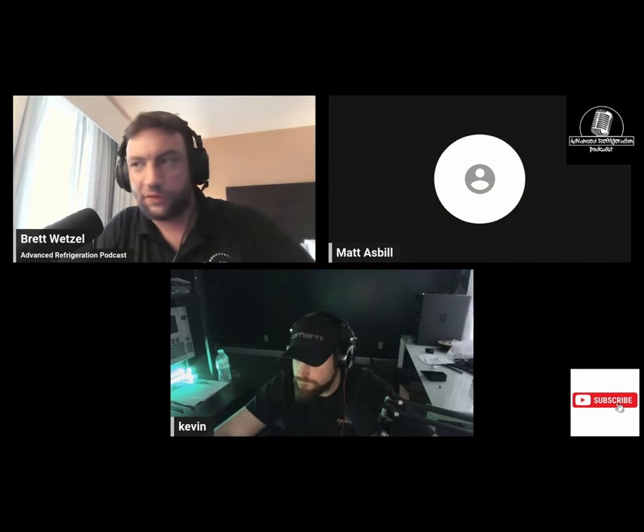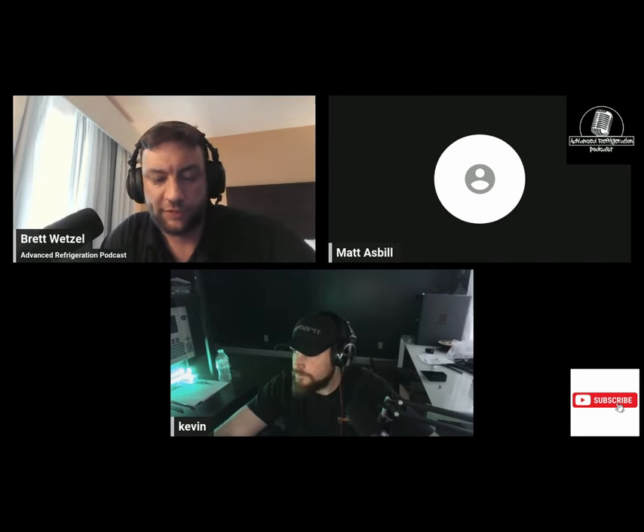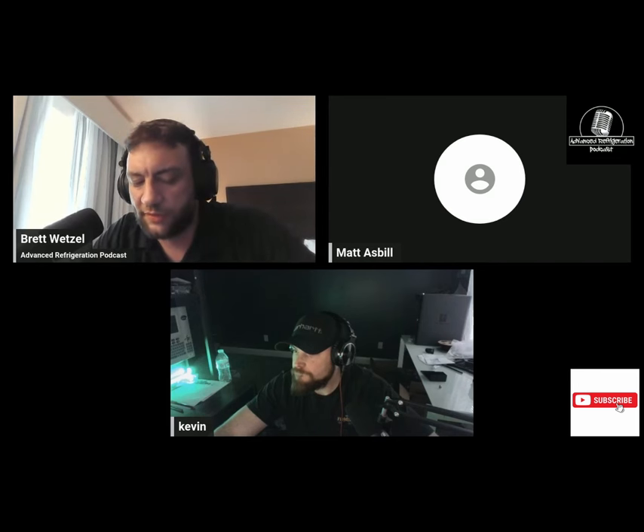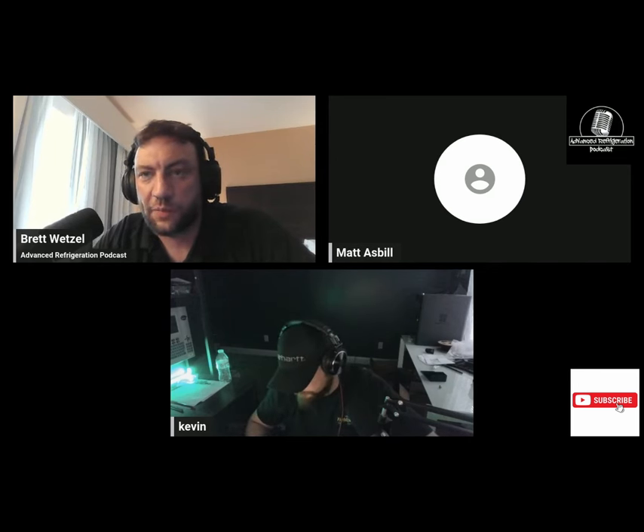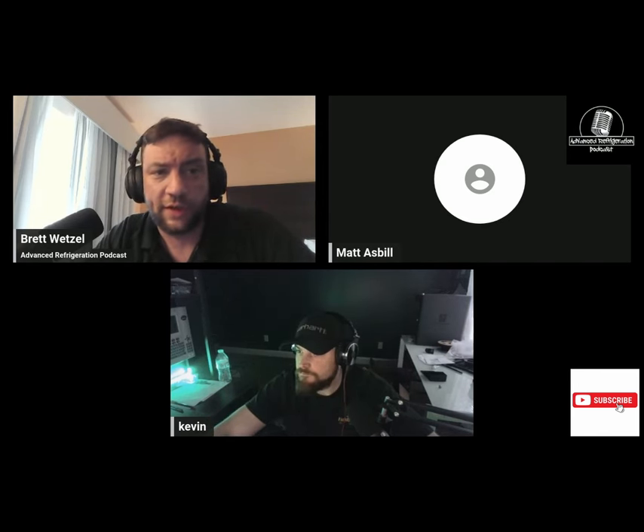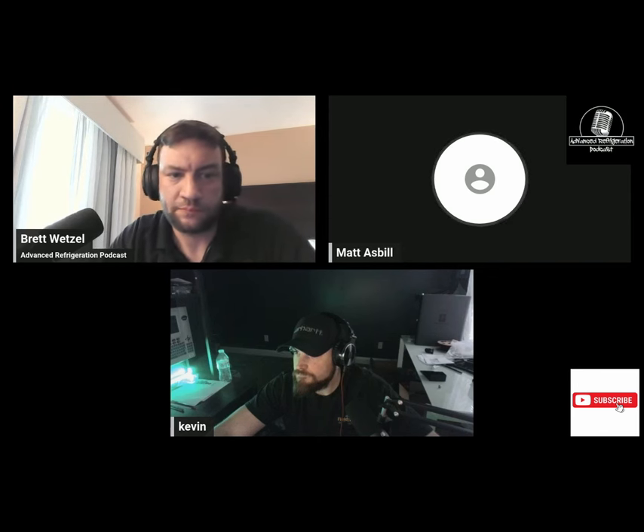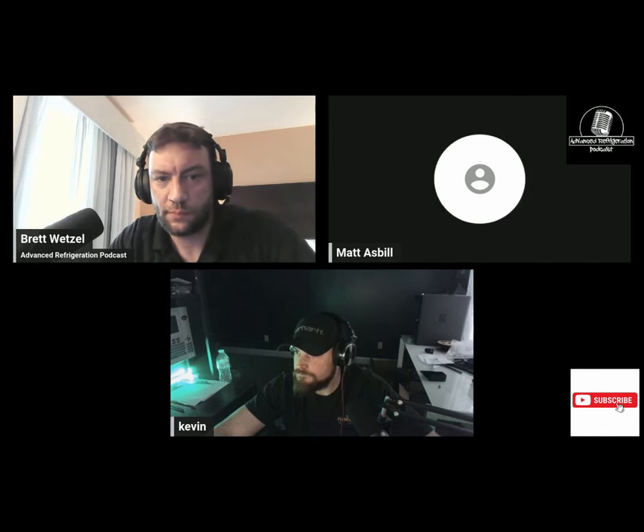Matt has been on with us before — it turned into two episodes because we talked for two and a half hours. Tonight I wanted to delve into why sometimes we get higher voltages than what we typically expect. Matt explained that if the unit is programmed for 480, we should typically get 480 at 60 Hz, and about half of that at half the frequency, because it changes both frequency and voltage. That's the basics behind the volts per hertz term — most open loop drives follow that linear pattern, zero to 460 volts is zero to 60 Hz, which is zero to nameplate base speed of the motor.